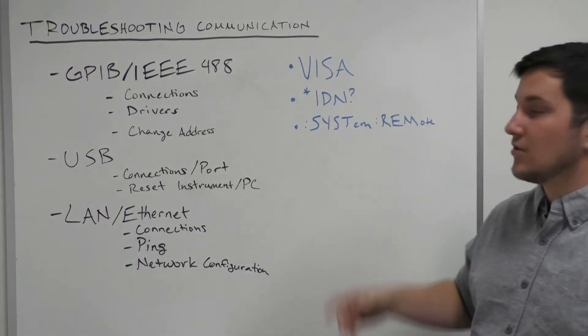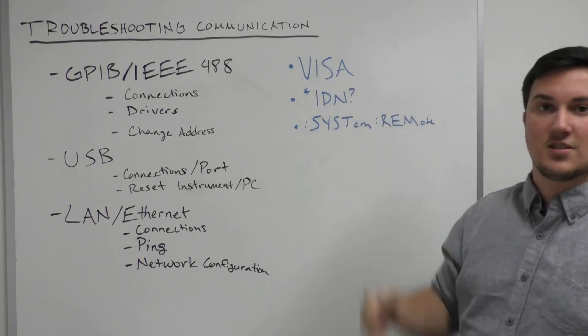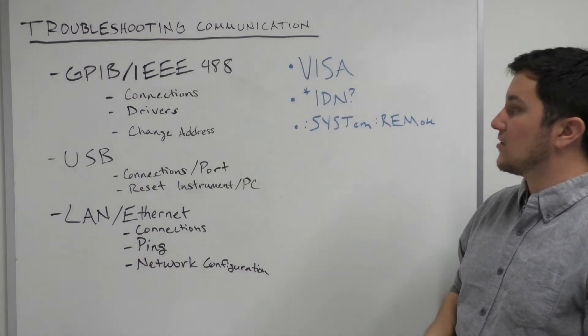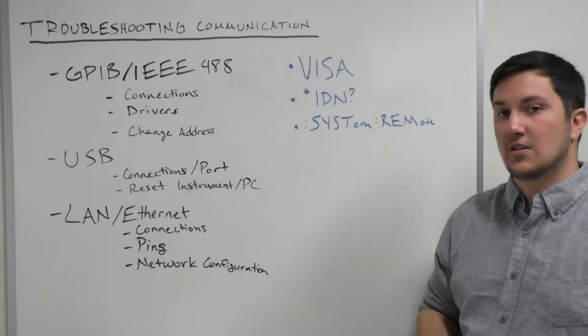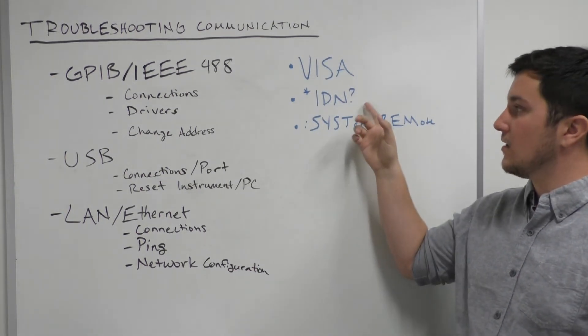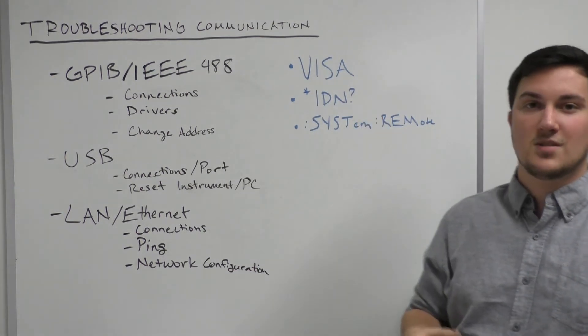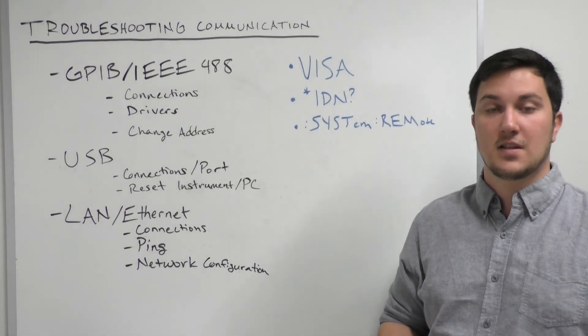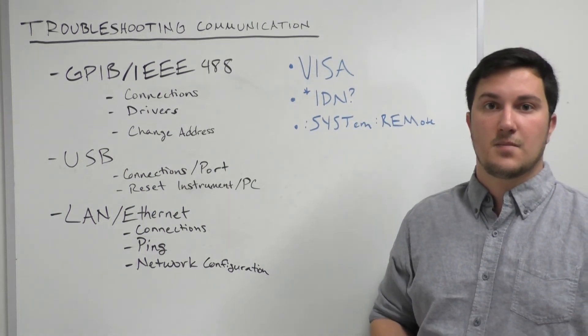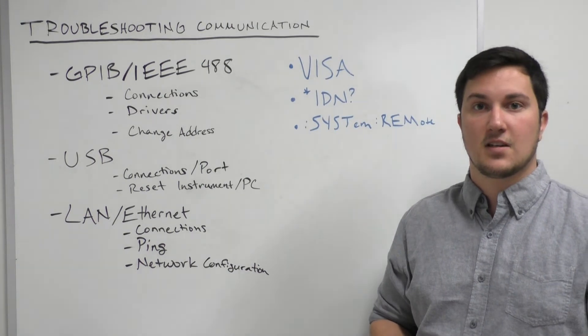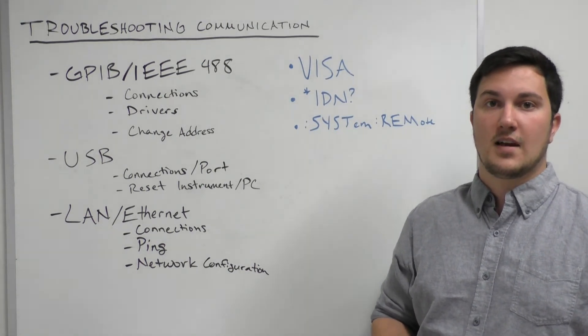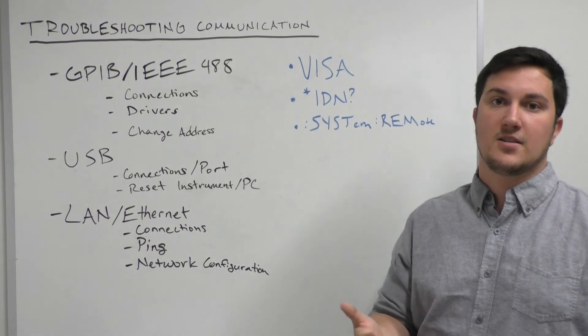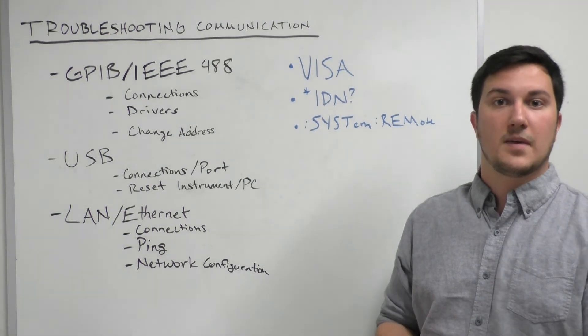In general, you want to make sure that you have a VISA installed, such as TekVISA or NI-VISA. If you're still having communication issues, you're going to want to use a *IDN query. You can use this in any kind of programming interface — some of the easier interfaces might be the TekVISA Talker/Listener or the NI-VISA NI-MAX input/output functionality that allow you to send one command at a time.